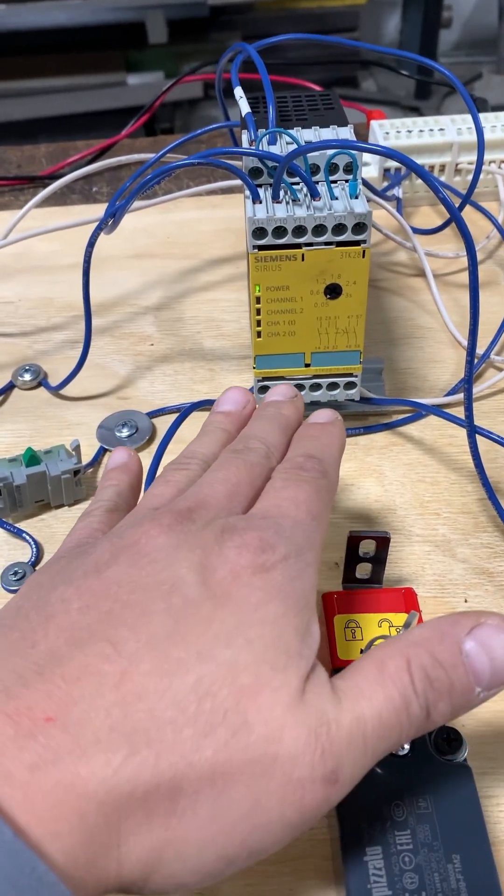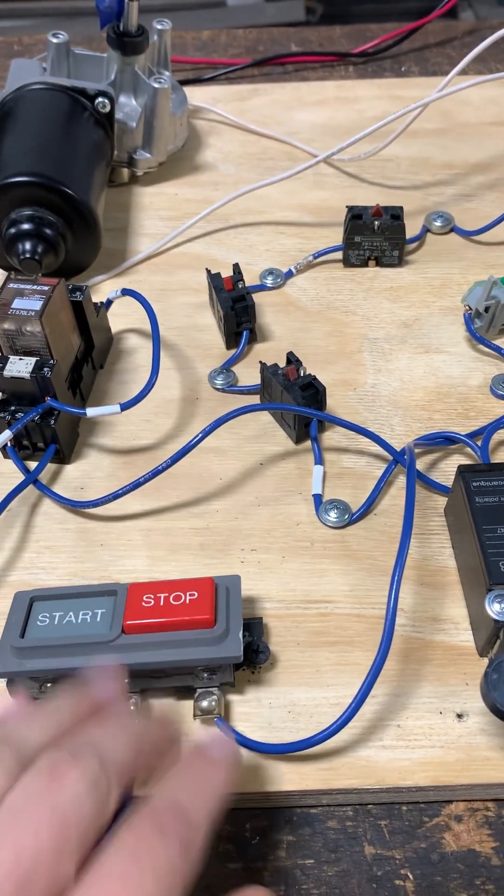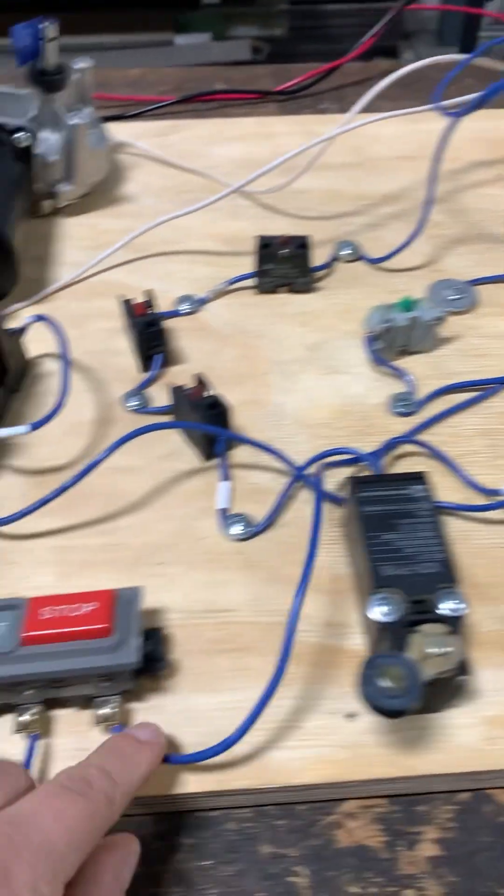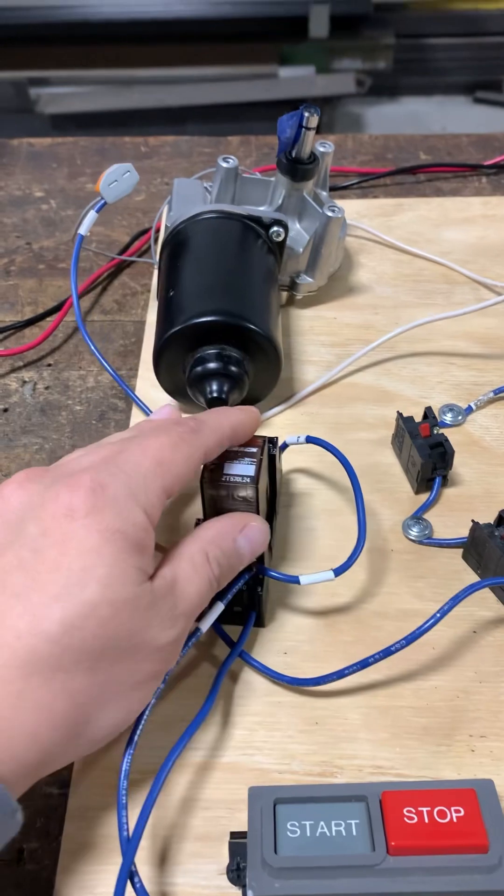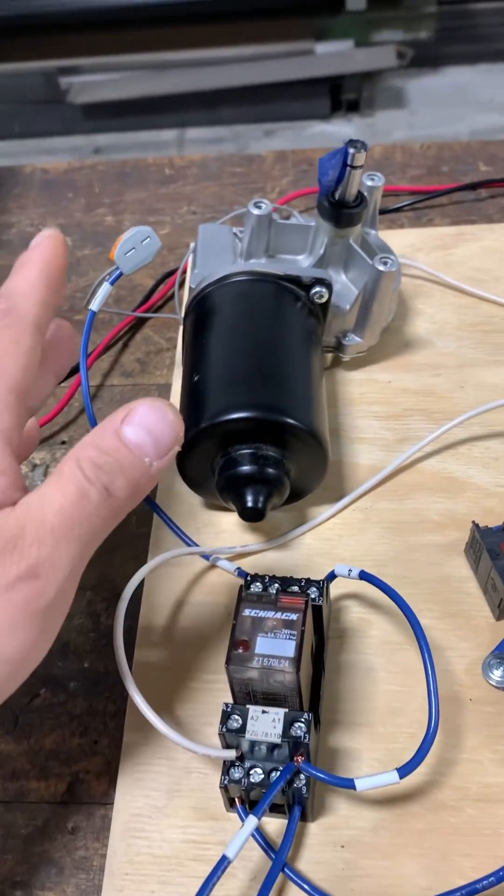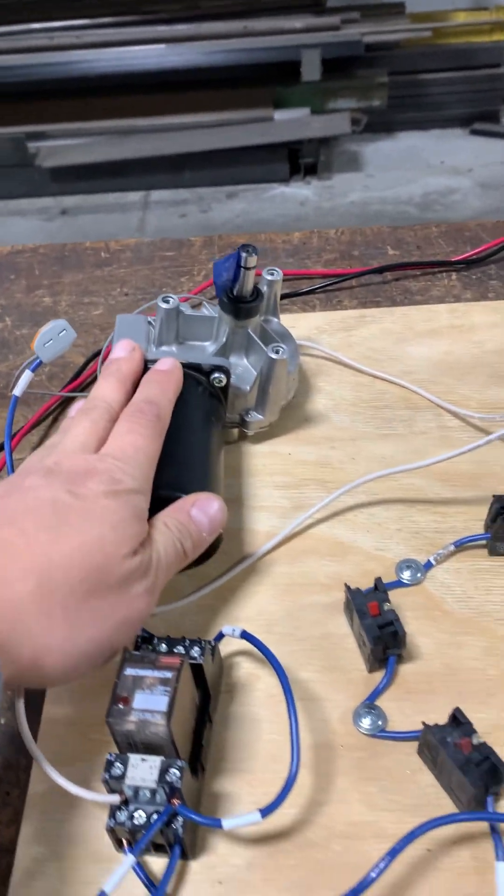The safety relay then closes another normally open set of contacts from the relay over to the stop/start. You have power coming from the safety relay into the stop, coming out from the start, then energizing a relay. And then this ice cube relay is going to turn on this DC motor.